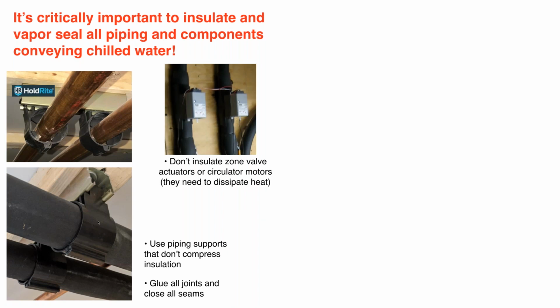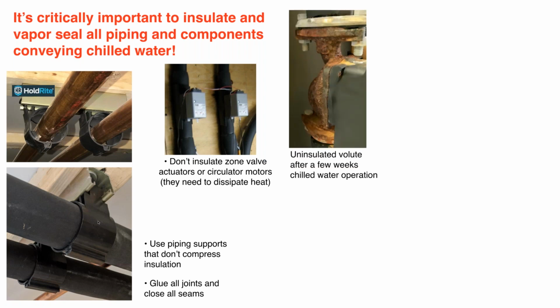If you're doing zone valves, you definitely want to insulate the valve bodies, but not the actuators, especially if those zone valves are going to function in heating. In the heating mode, that actuator has to dissipate some heat. And again, don't insulate the actuator.